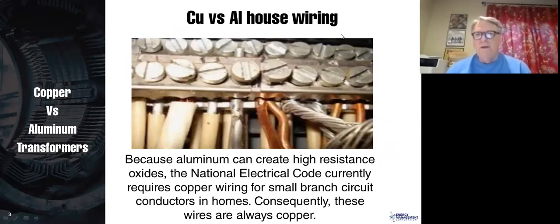In house wiring, you can see there's some aluminum wires and some copper wires, and aluminum wires in these types of installations can end up developing an aluminum oxide, and it has caused some of those terminals to become hot. In house wiring, the wiring to lights and receptacles and things of that sort, the National Electrical Code asks you to use copper. So in all modern houses, at least in the United States, complying with the NEC, they use copper wiring. If you're outside the United States and listening to this, then your country may have different standards.